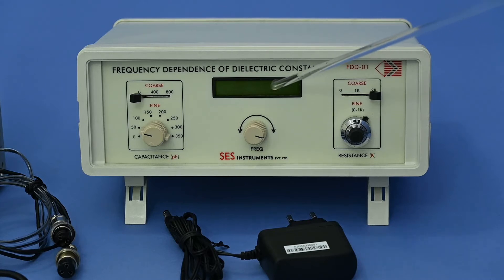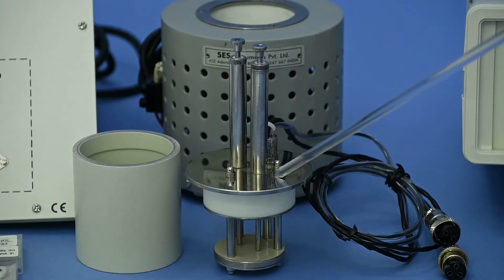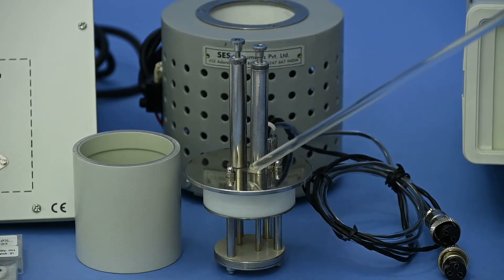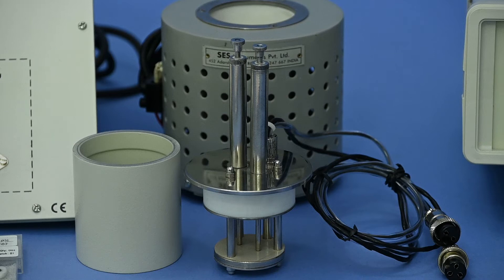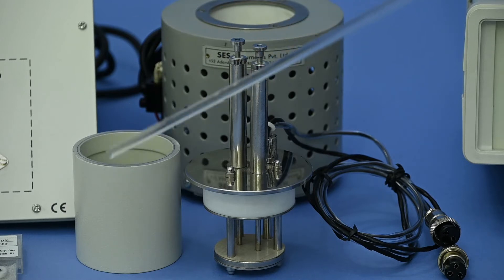And digital panel meter. Probe arrangement has two spring-loaded probes mounted in a suitable stand which hold the base plate with RTD sensor. This arrangement is used as a lid of the oven or arrangement stand.